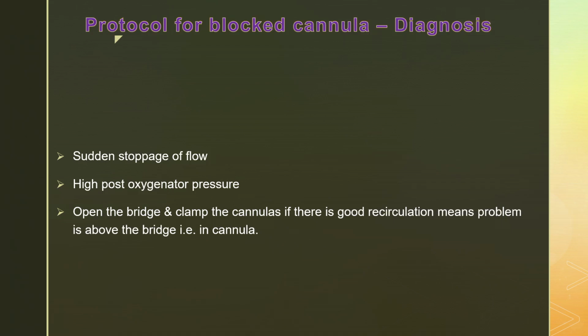Okay. The next is a blocked cannula. Okay. Now, a blocked cannula and accidental decannulation are going to be a nightmare. You can suddenly see that there is total stoppage of flow. There is no flow going on. So how will you see whether it is a blocked cannula, a blocked oxygenator or a blocked circuit?